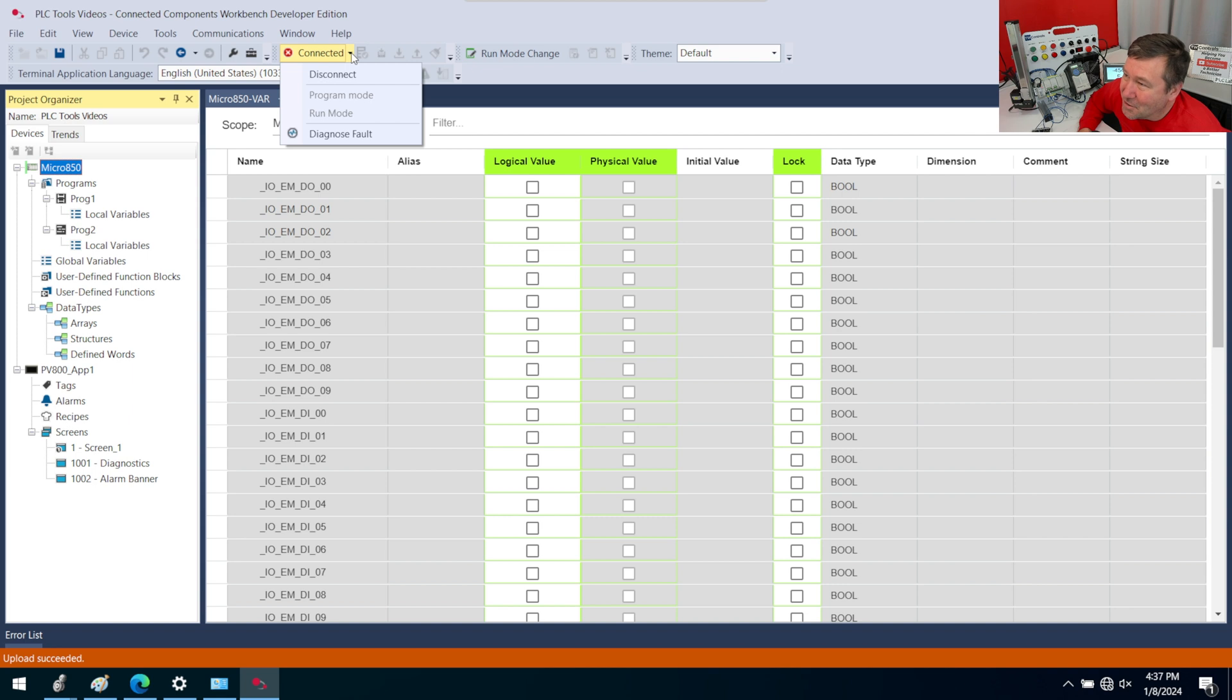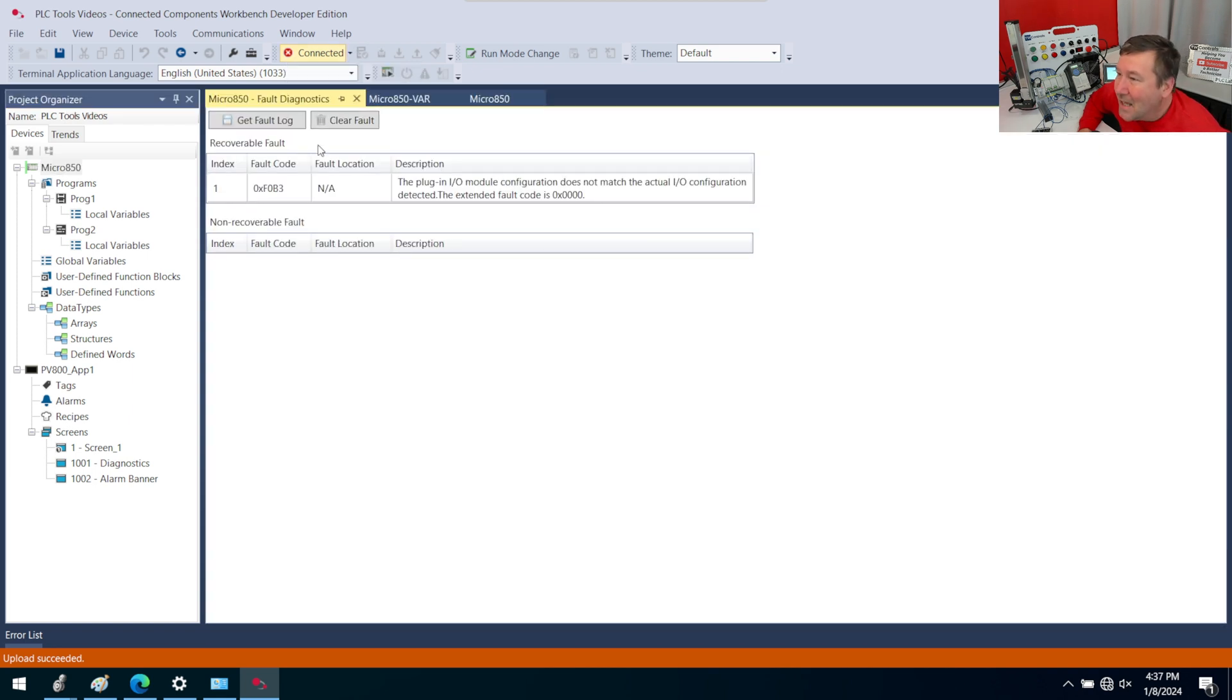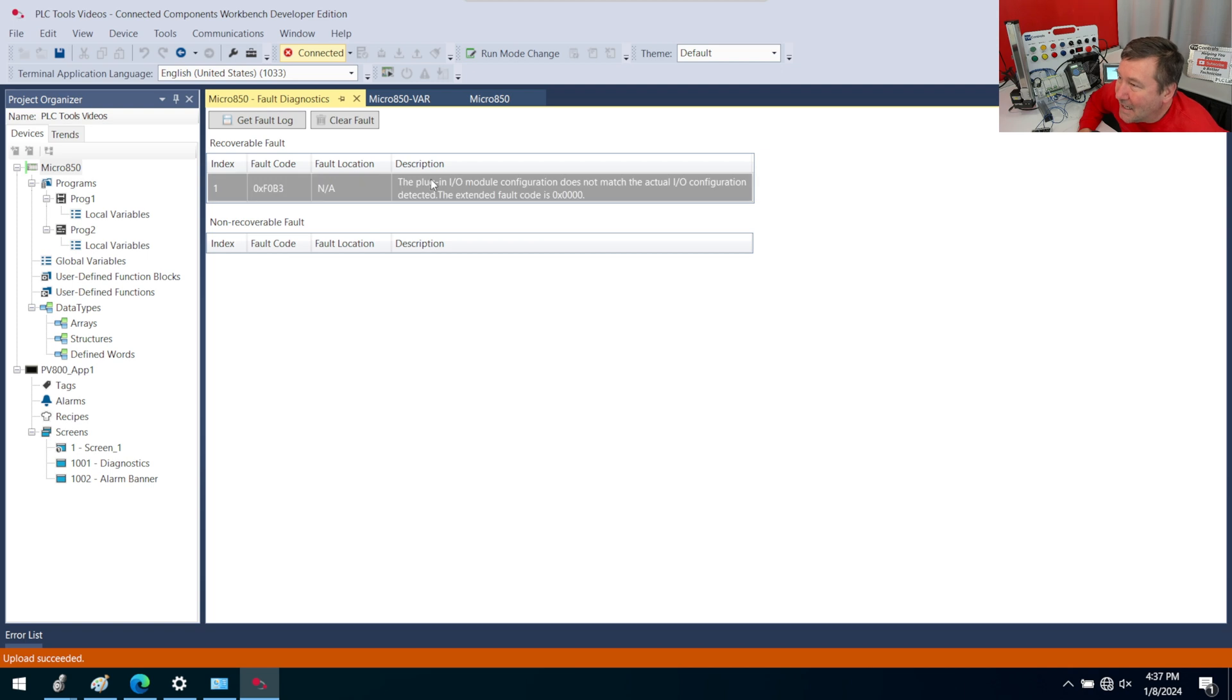We want to hit the dropdown beside it and go to diagnose faults. And it says right here: the plugin module in the IO configuration does not match the actual IO configuration.